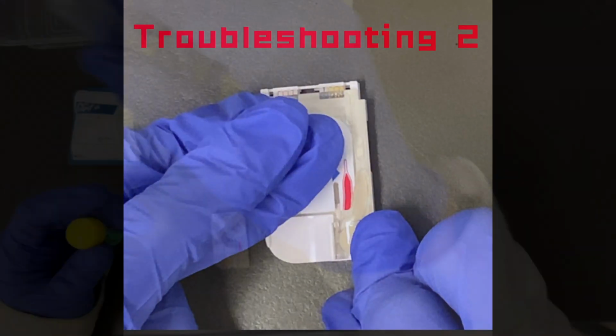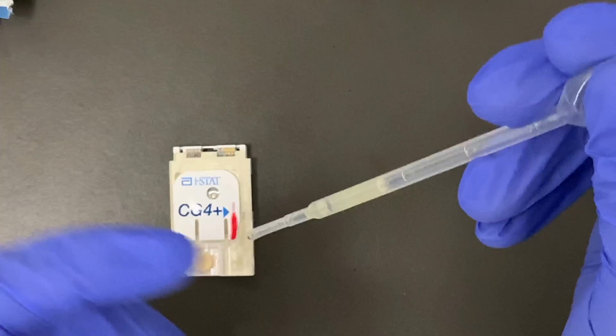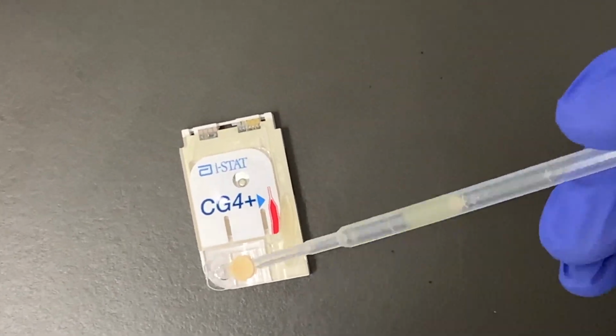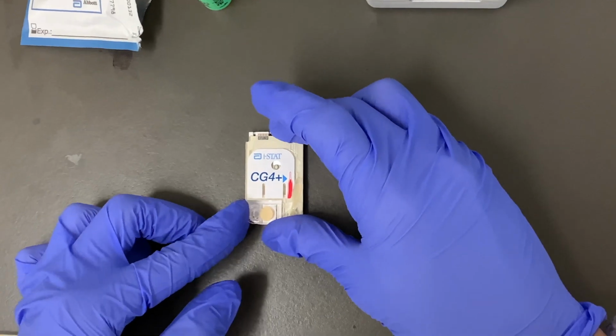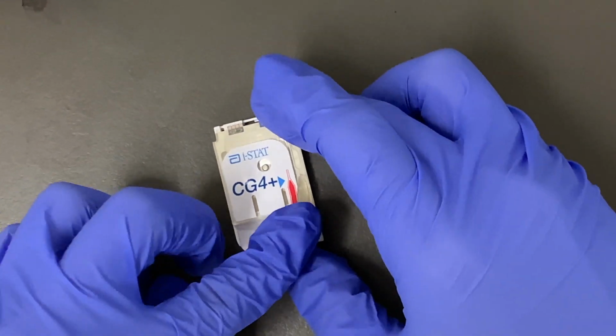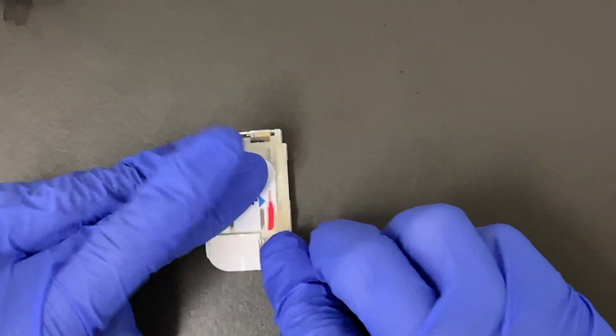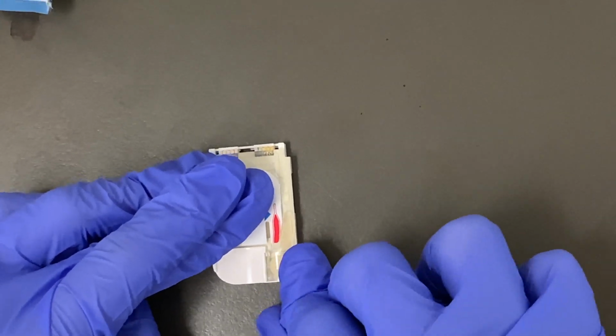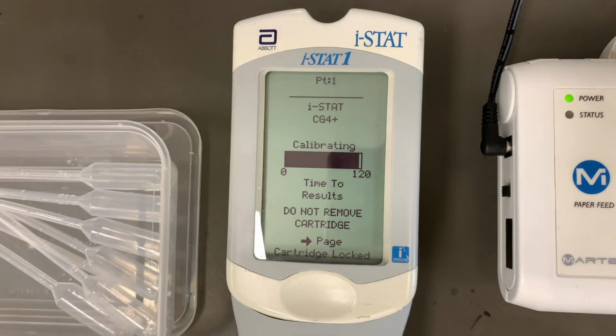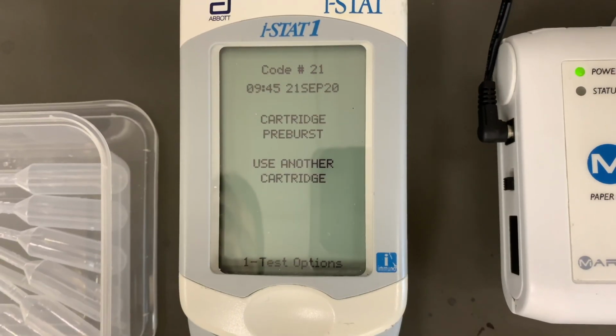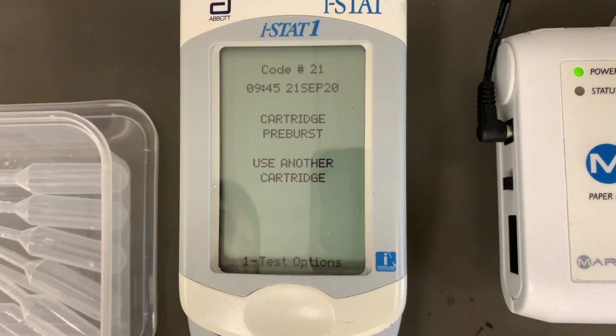The second issue we will demonstrate is the mishandling of the cartridge. Again, we are doing the procedure as usual. As you can see here, when the operator closes the flap, his finger accidentally presses against the center of the cartridge. After inserting the cartridge, the screen displays an error code 21, which indicates cartridge pre-burst. To avoid this error, make sure you're handling the cartridge in a suitable manner.